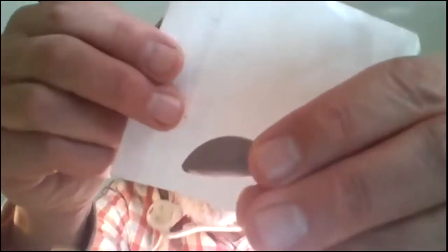And you will notice this on your fitting software. When you're fitting hearing aids, you're going to be asked what kind of dome you want to use in your hearing aid. And what I mean by dome, of course, and some of you may know already, is, let me pull out my little bag of tricks here. See if I can find a dome. There you go. What kind of dome do you want? Do you want a dome with a lot of holes in it? Look at the holes. 4 of them. That's a big vent. Okay? Do you want a vent with lots of holes in it, or do you want a vent with fewer holes in it?